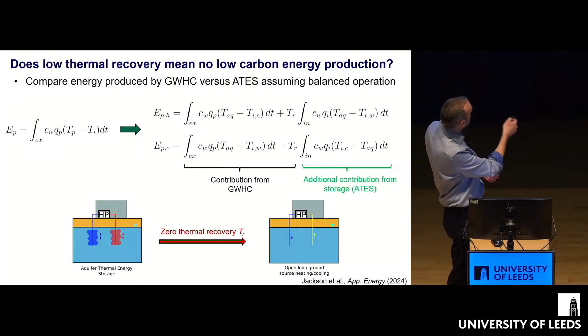And we've done a whole bunch of modeling to look at which might be optimal in what situation. So this is basically energy produced from an ATES system versus a standard open loop system, and we always lie above the gradient of 1 - you always get more out of an ATES system because on average you don't have zero thermal recovery.